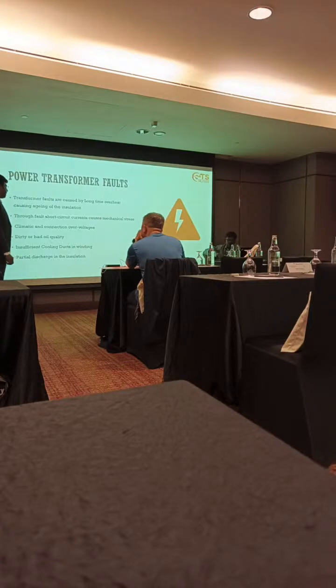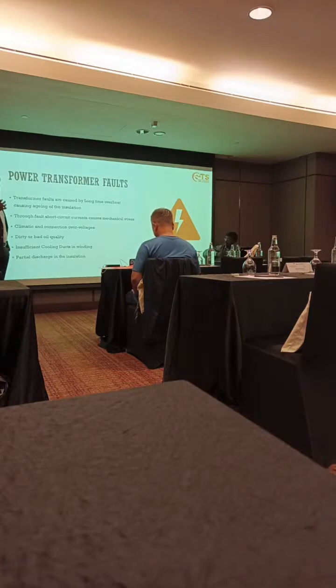Another one is the climatic condition, maybe lightning or low voltage, which may lead to transformer failures. And third is bad oil quality. Oil quality is very important for a transformer. Due to aging, the oil will absorb moisture. Once it absorbs moisture, it will lose its dielectric strength. Once the dielectric strength of the oil is weakened, it will also lead to a decrease in insulation level. So usually, in a transformer, let's say this is a core.